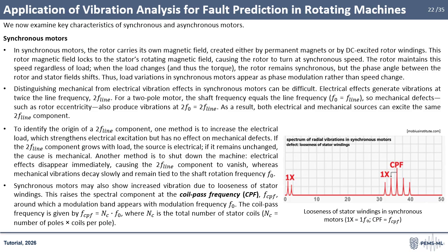Another method is to shut down the motor. Electrical components disappear immediately, whereas mechanical vibrations decay gradually. Finally, synchronous motors may also exhibit increased vibration due to stator winding looseness, which raises the vibration level at the coil pass frequency.